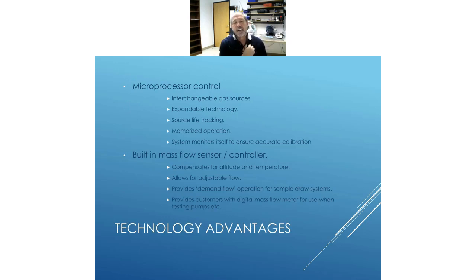The instruments are microprocessor controlled, so you can buy 5 or 6 different generating gas sources for one instrument. So one instrument will do all 3 of these gases we're talking about today and several more. By swapping out the generating source, it can do chlorine, chlorine dioxide, and ozone. They're also expandable. We have other gases that we're not talking about today. The sources are tracked by life, so when you turn it on, it tells you how much life is left. That's the consumable part of that instrument, the source. So it tells you so that you don't unknowingly run out.